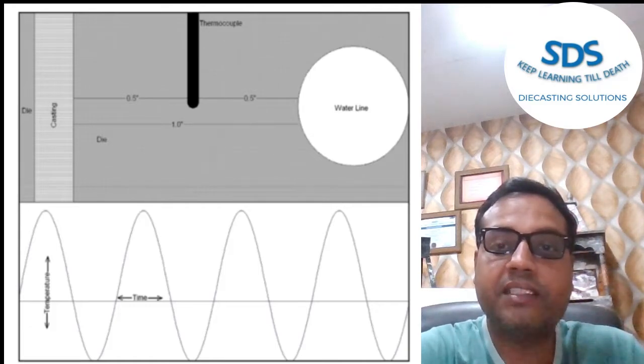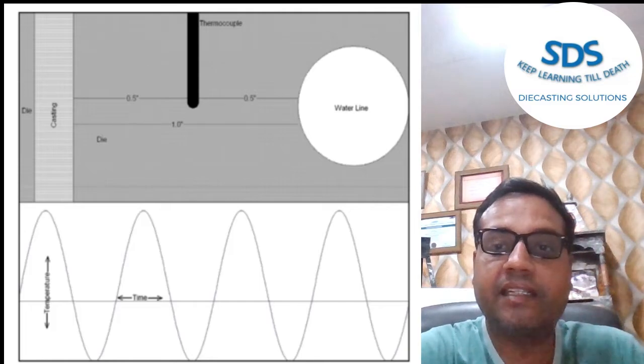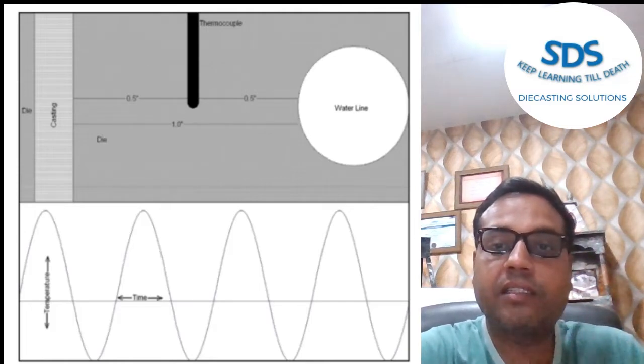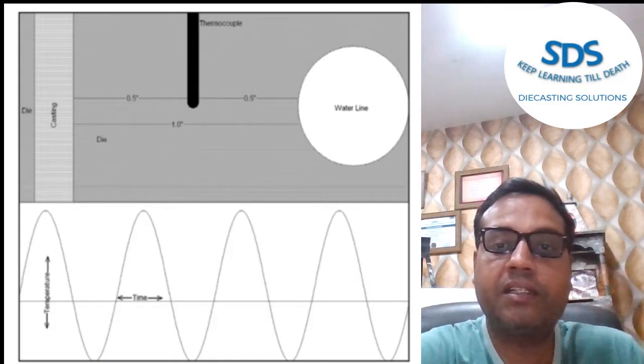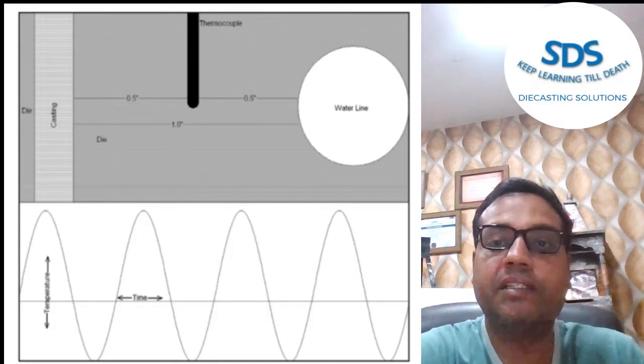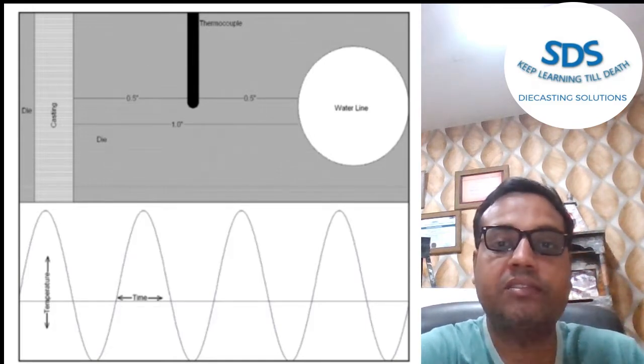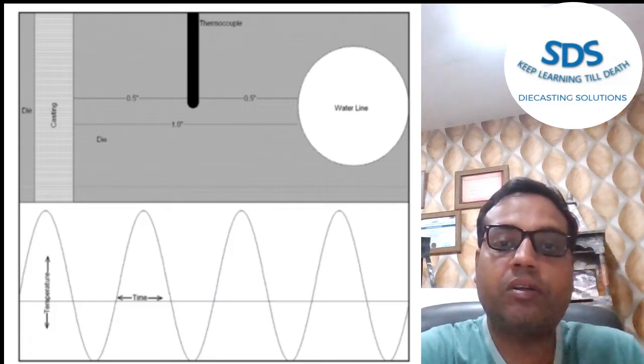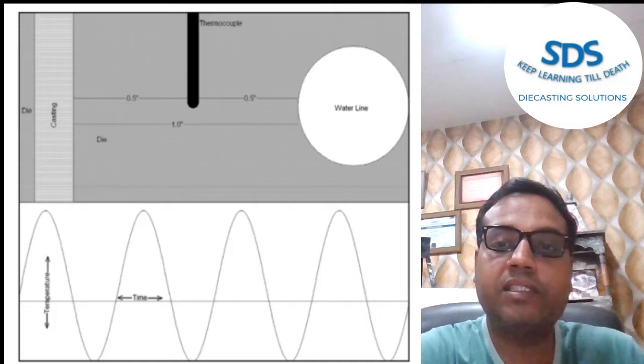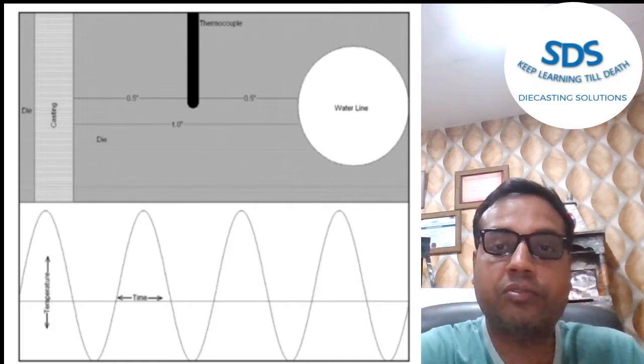Once the thermocouple goes below the set point and the water line turns off, there is a deficit of heat in the die. The temperature at the thermocouple continues to drop below the set point until the heat builds up enough to cause the temperature to rise again. Because the die casting process is a thermal process, closed loop control is usually not a good approach for thermal control.